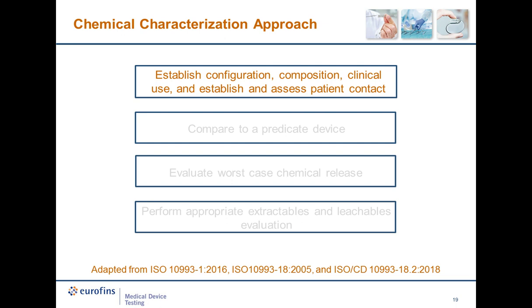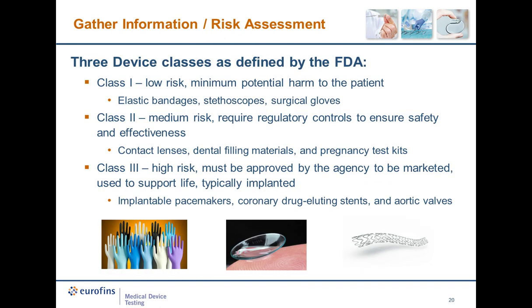Again, the first step in the risk assessment is establishing the configuration, composition, and clinical use of the device. First, let's establish what types of devices can be appropriately assessed using chemical characterization. Primarily, chemical characterization is used for Class 2 and Class 3 medical devices since they pose an elevated risk to the user or patient. If the device does not have any direct or indirect tissue contacting components, typically no biocompatibility information would need to be generated.